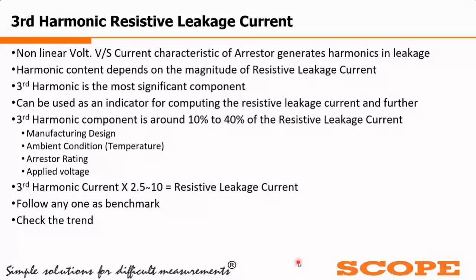So as I was telling, the nonlinear voltage versus current characteristics of the arrestor generate the harmonics in the leakage current. So how the leakage current comes into the picture, or how the harmonics are getting generated, that is the first question. This harmonic content depends on the magnitude of the resistive leakage current. So harmonic content will increase if the resistive leakage current is increasing. Now these are not our claim. It is what the researchers have found.